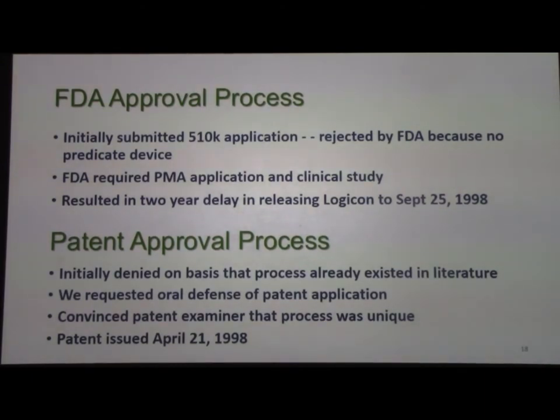And the other interesting thing is about what the FDA worries about. You know, they ask very few questions about the technology. That's not the way they did the review. The things that they review are the results of your clinical study, whether or not you had a truly unbiased database. They worry terribly about that, because it's easy to jury rig these things with certain databases. And the labels afterwards, what claims you make. You got to be really careful with claims.